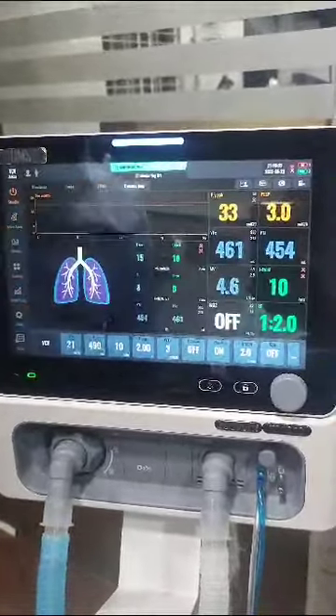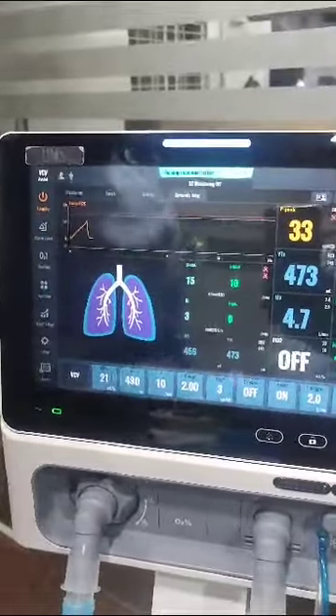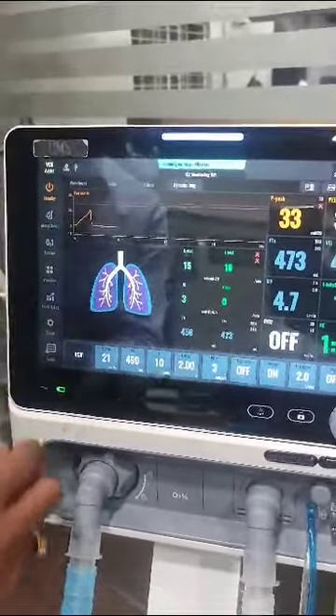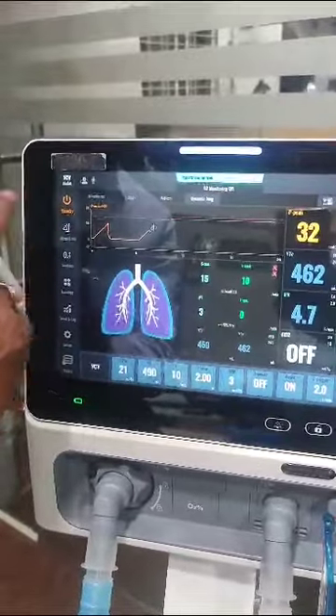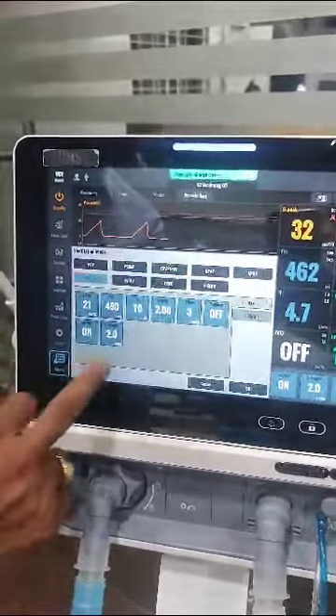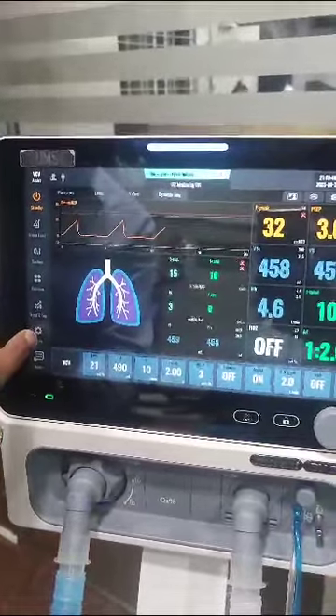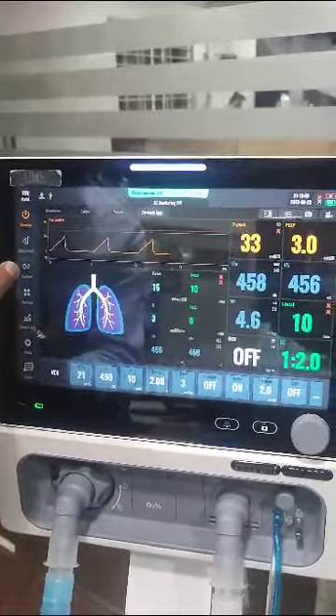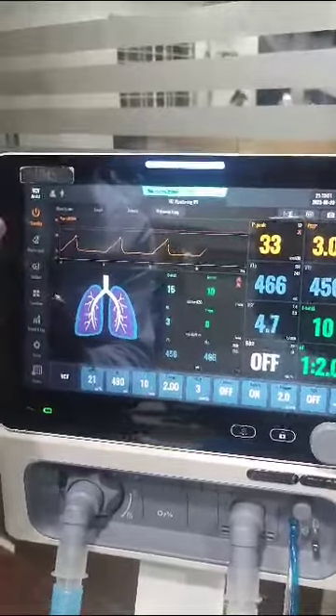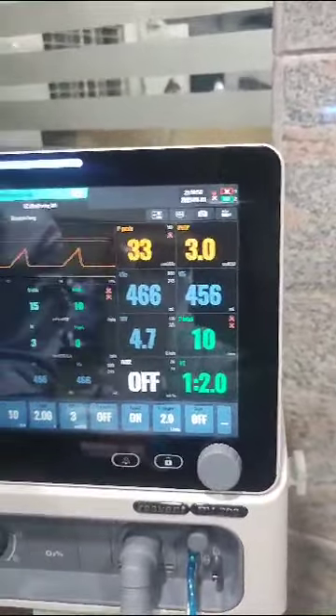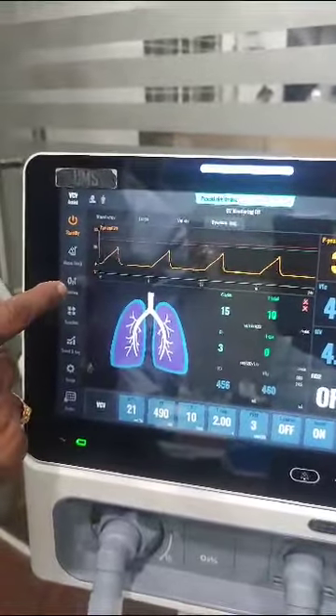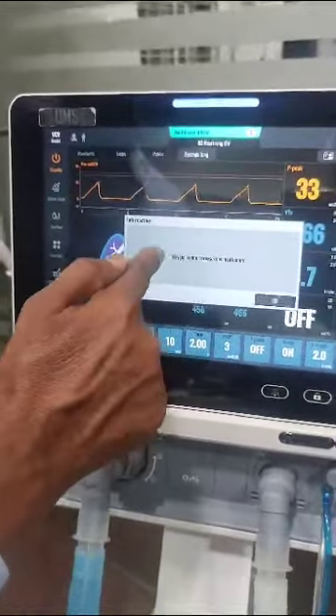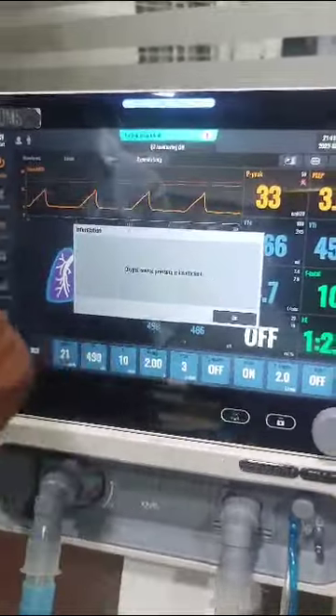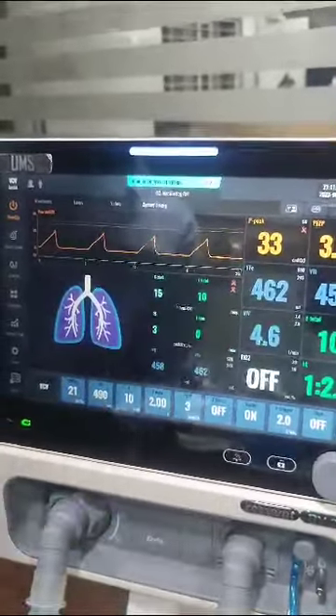Now this is the dynamic lung page. This is also very useful, and this is your extra settings. When you want to go to standby, you can choose here. If you want some modes, you can touch here and these modes will come. Then you have setup, trends, functions, suction and alarm limits. Any alarm, you can touch alarm and set minimum and maximum here. During suction, if you want 100% oxygen, you touch it and it automatically gives 100% oxygen. Now oxygen is not connected, so the oxygen source pressure is insufficient. That is why it is not giving oxygen.